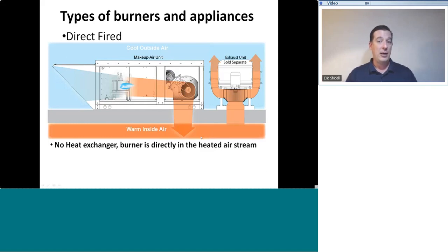One of the things to be aware of about direct-fired units, which makes them a bit more complicated from a service standpoint, is that the makeup air unit is controlling to discharge air temperature. So say we want to control the temperature of the air coming out of the unit at 70 degrees all the time. When the outdoor air temperature is 70 degrees or warmer, there's no demand for heat. But as the outdoor air temperature falls, we need to operate the burner in order to maintain that 70 degree air temperature. Now, it's not practical to have that burner cycle off and on to try to maintain air temperature, because otherwise we're going to get warmer, colder, warmer, colder, warmer, colder as that burner cycles on and off.